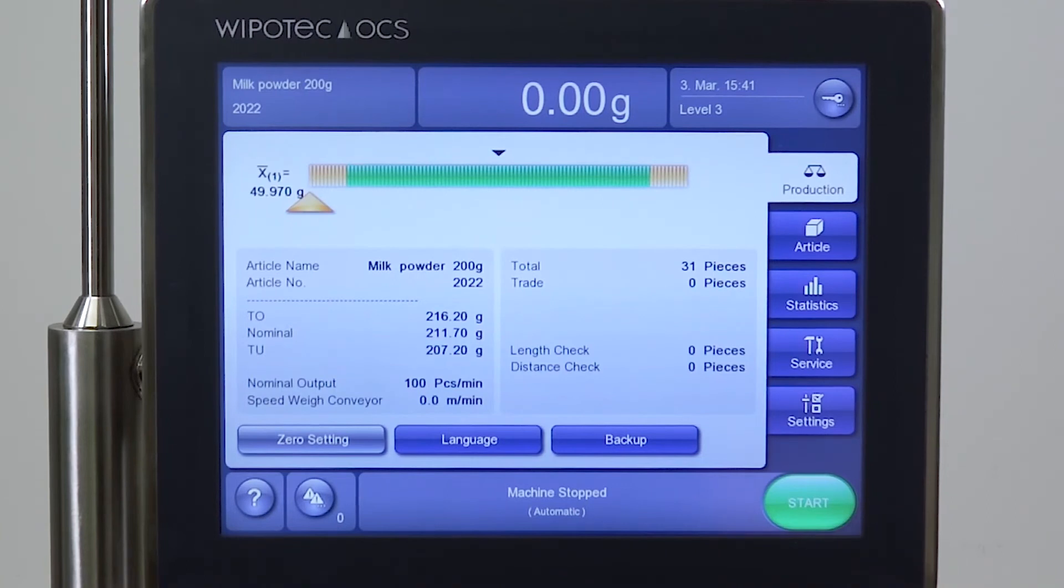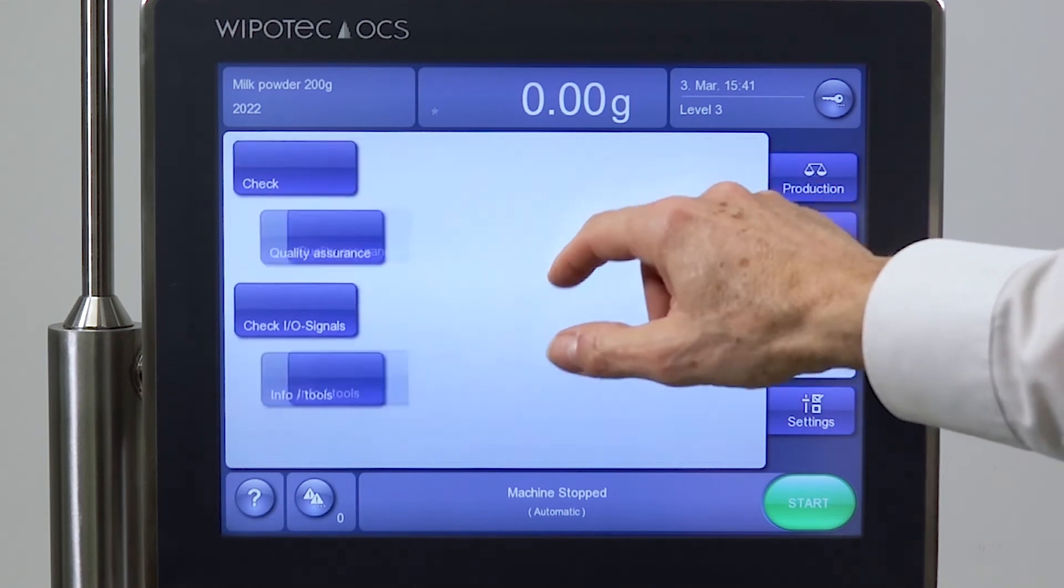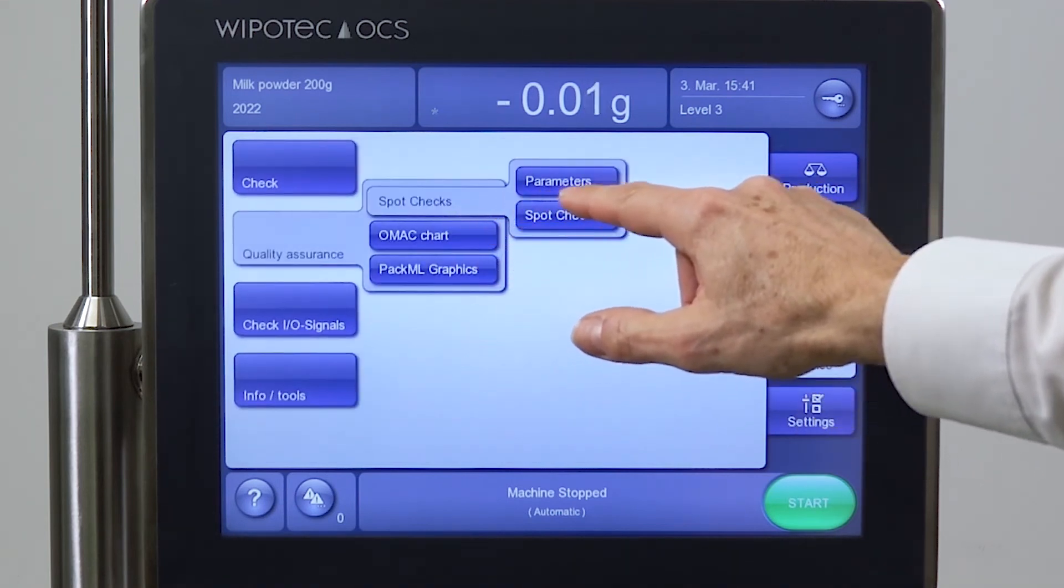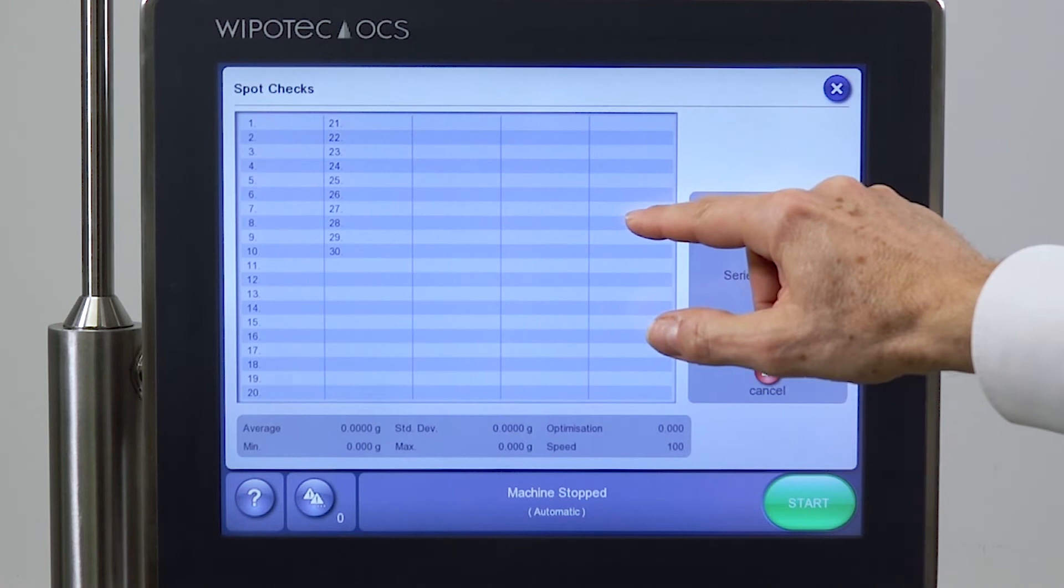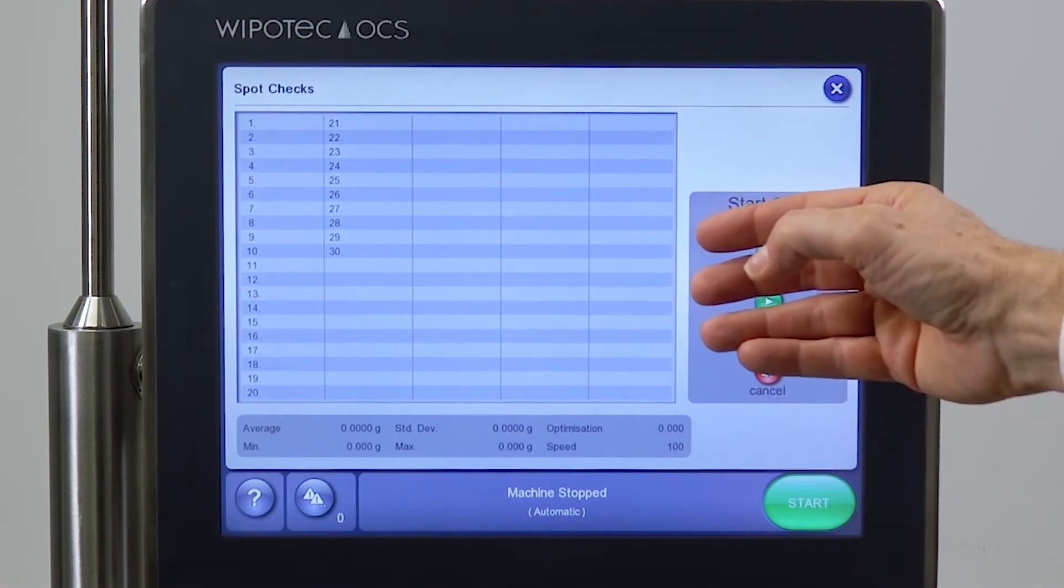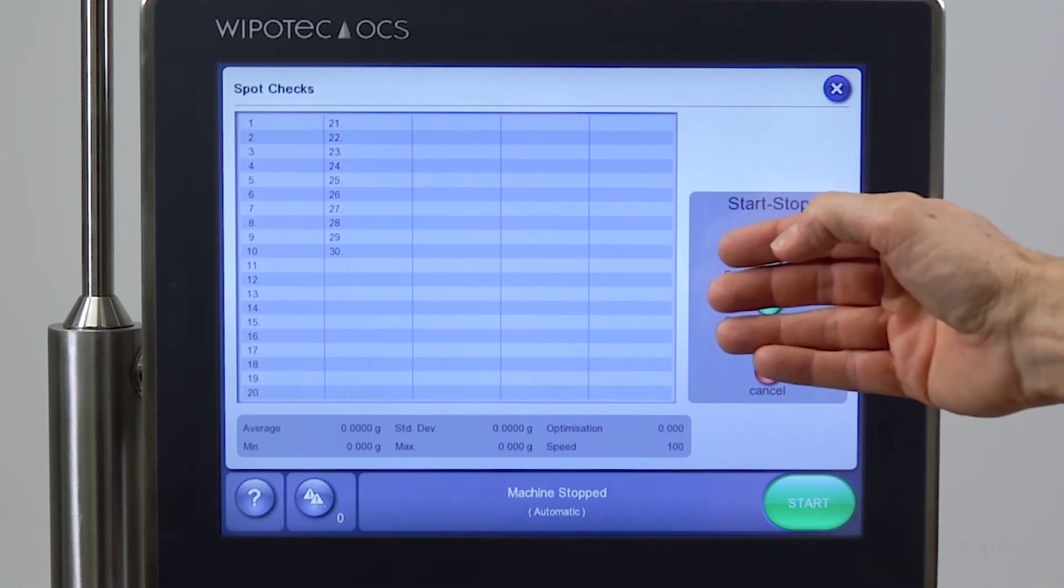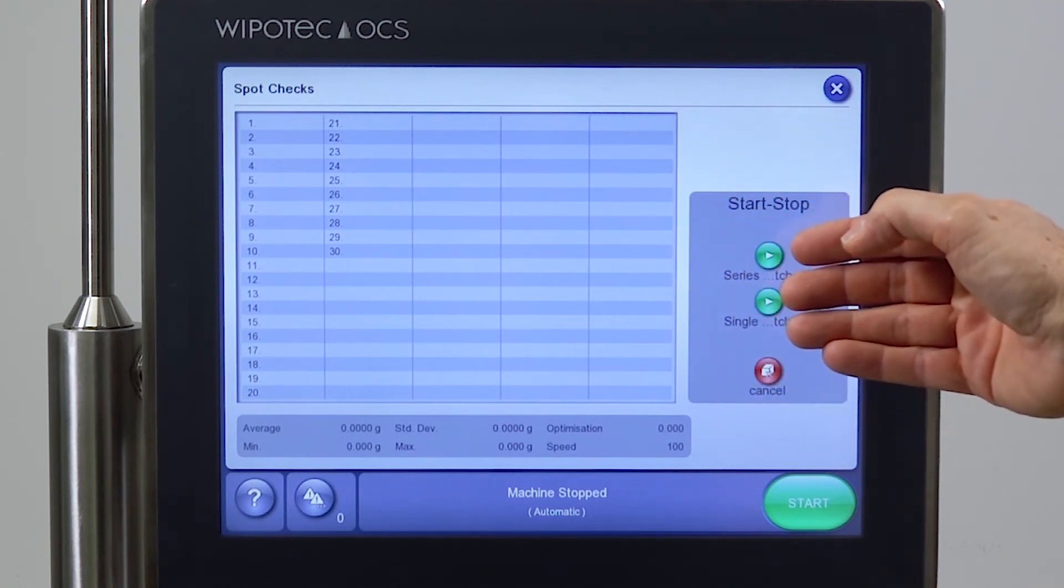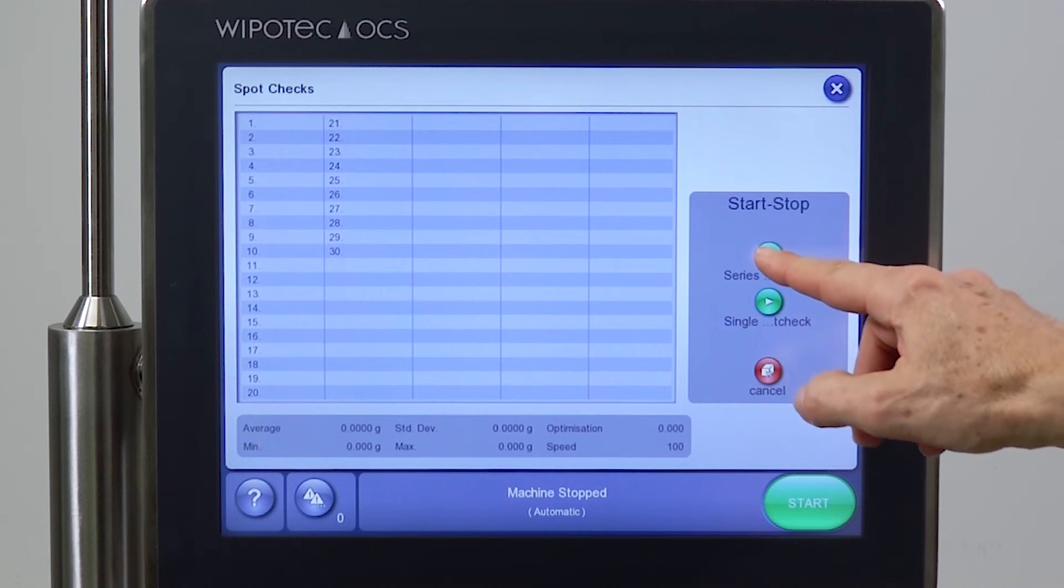In order to verify the uncertainty of a checkweigher we could enter the spot check mode and try with the spot check to see what is the repeatability of a product. In our case we would be using 30 times the trigger of the weigh cell to verify a weight stone of 50 grams.